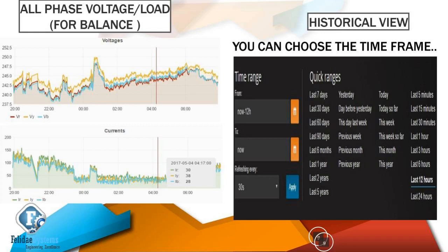At the same time, from the consumer side, the quality of power is determined by some internal factors. Again, harmonics is one — if we have a lot of switching load, harmonics will be generated by ourselves. The second is power factor: if we have low power factor, due to more inductive load, the current of the entire plant will be more, and safety will be compromised because we are running more current in the cables.